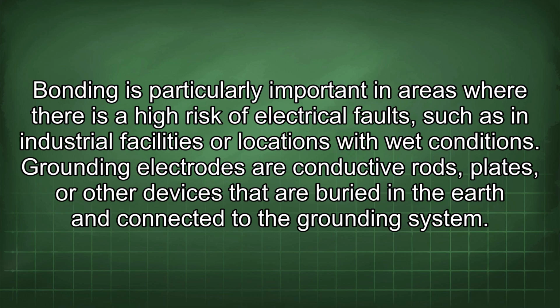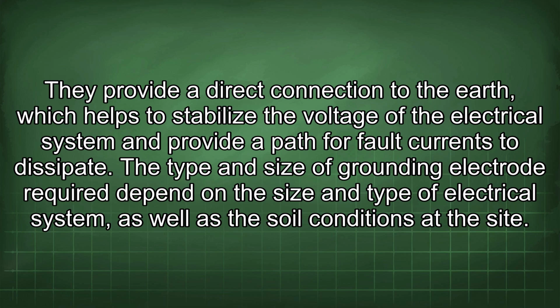Grounding electrodes are conductive rods, plates, or other devices that are buried in the earth and connected to the grounding system. They provide a direct connection to the earth, which helps to stabilize the voltage of the electrical system and provide a path for fault currents to dissipate. The type and size of grounding electrode required depend on the size and type of electrical system, as well as the soil conditions at the site.